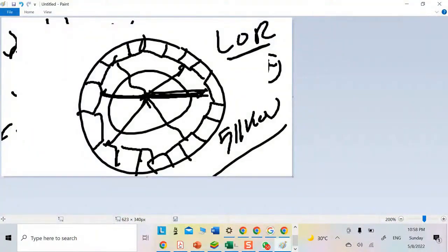The decay time of this electron should be fast, and the light fraction or the light photons emitted should be large. The fourth point is that the photoelectric interaction ratio occurring within the crystal should be better or higher than the Compton scattering to improve resolution and avoid scattering photons that could affect image quality. These are the properties based on which the crystal is selected.